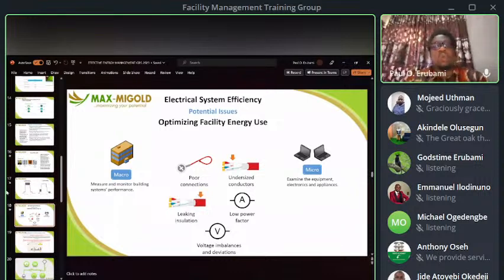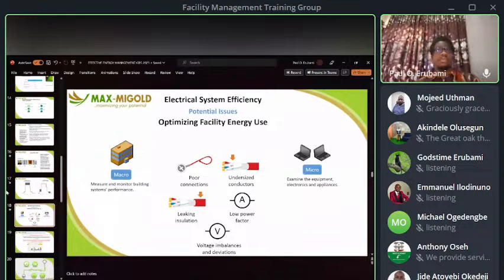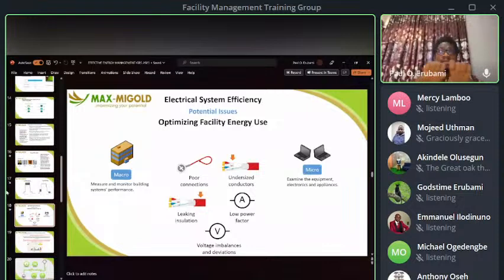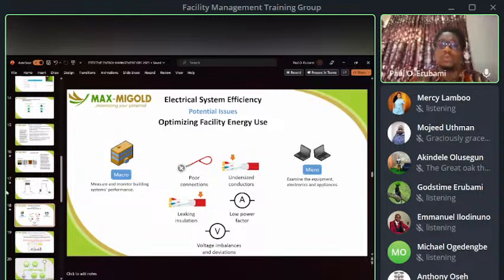Other things that affect your energy use that you need to watch out for: poor connections and dirty connections. This is basically what happens with electricians - they don't want to use proper connectors, they cut and peel and twist cables. Those joints aren't tight, leading to poor connection issues. You have undersized conductors that get hot when equipment is in use, sometimes beginning to melt and even leading to fire.